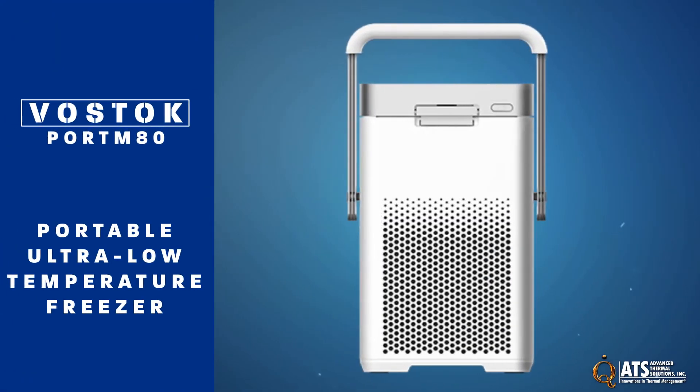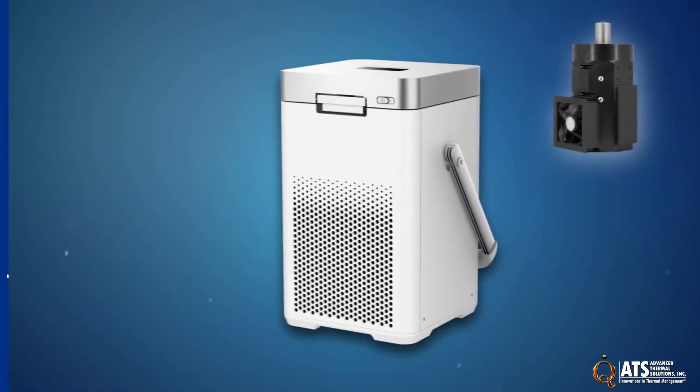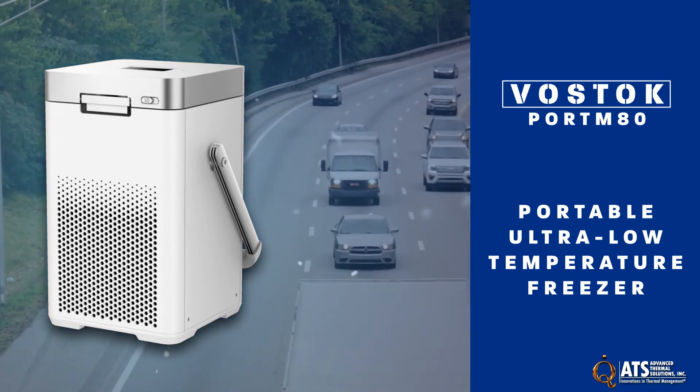The Port M80 is a portable freezer that improves the transportation of medical products and samples with its compact size, lightweight design, and one liter storage capacity. With its Stirling refrigeration technology, the Port M80 uses helium as the refrigerant and is well equipped to handle vibration and bumps due to transportation.